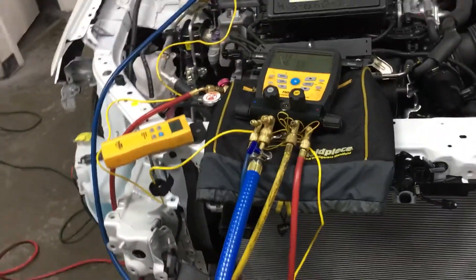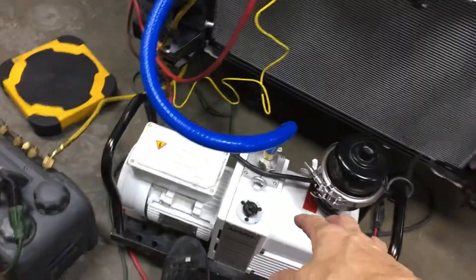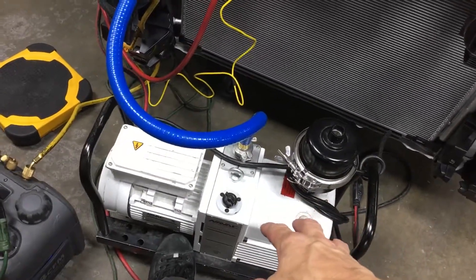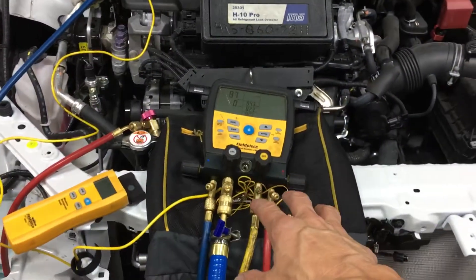Now I'm about to draw a vacuum on the system. As you can see right now, I have the 12 CFM pump that can go down to 3 microns, and the 8 CFM Fieldpiece that can go down to 20 microns. They're both hooked up to my manifold system.